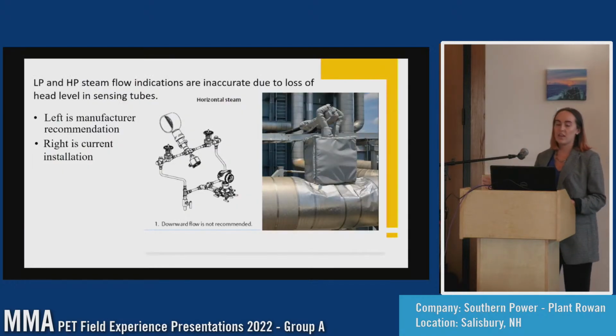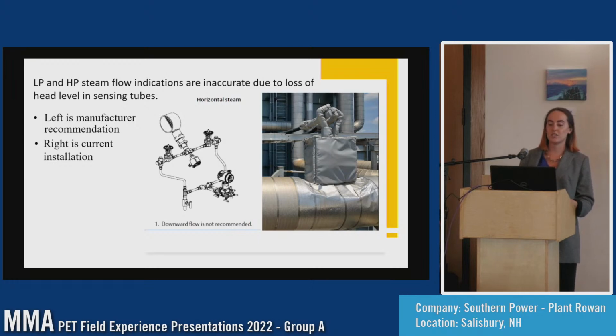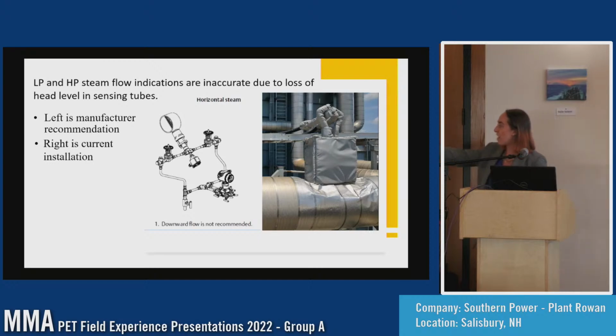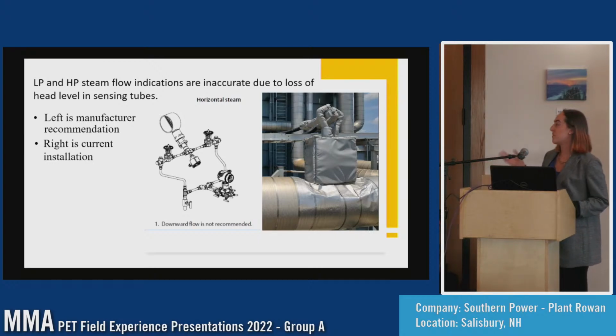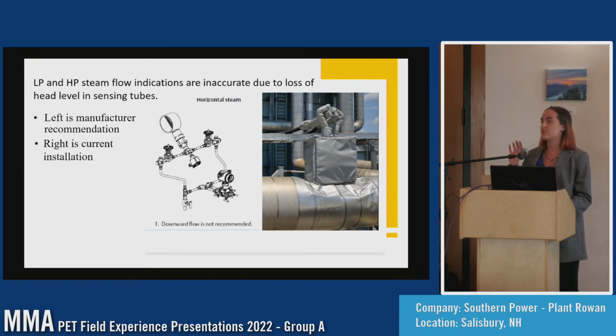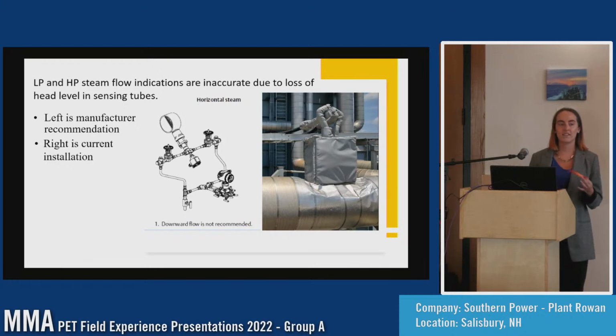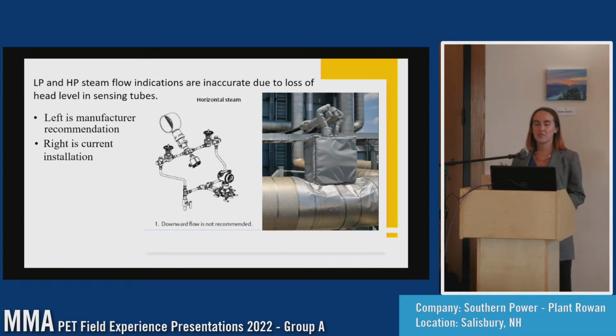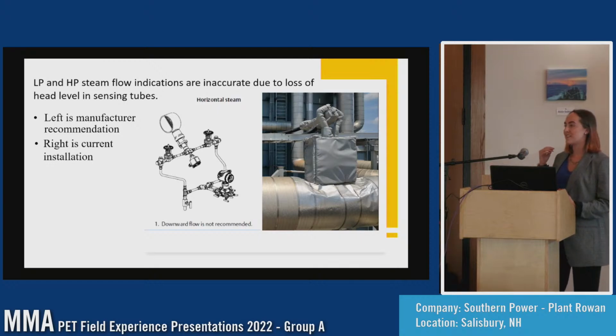So for my problem, the LP and HP steam flow indications were inaccurate due to the loss of head level in the sensing tubes. That right there is a picture of an annubar, which is the instrument they used to measure the differential pressure, which they then used to create a steam flow rate. On the right is the current installation they had, and on the left is the manufacturer recommendation. You can't tell, but they're upside down to each other.